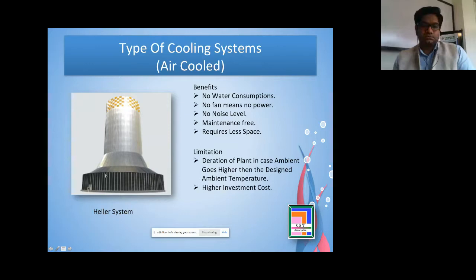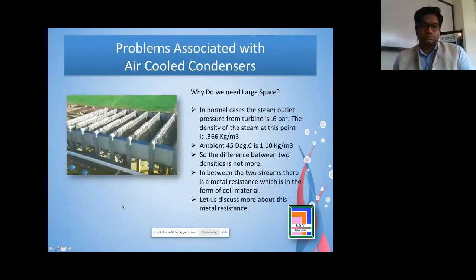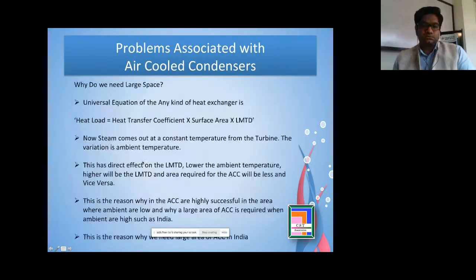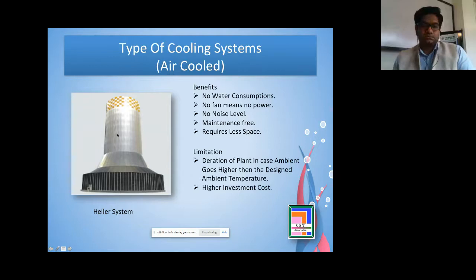In a Heller system, the coils, instead of going in a V shape like this one, are installed like this. And there is no fan over here. So with the differential pressure, the air blows over these fin tube coils, and then the steam is condensed. The benefit is there is no water consumption, because it's a completely air-cooled system. And secondly, no water means no power also. There is no fan, and no fan means no power. And if there is no fan, there is no noise level also. No mechanical moving equipment means it is maintenance free. There are no motors, no fans, no gearboxes, no belt, no speed increaser, no shaft. So this is a very good system.